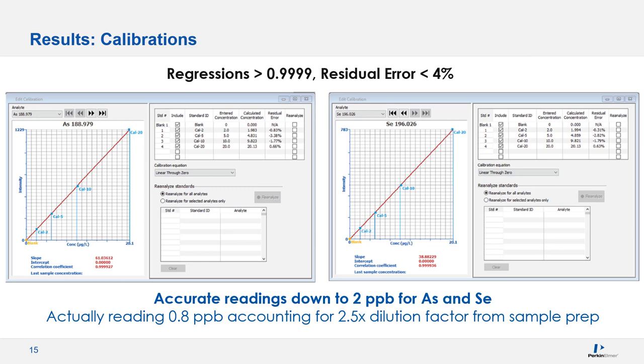Looking at calibration curve results: standards were made at 2, 5, 10, and 20 ppb in 1% nitric before reduction, then diluted 2.5x, so the actual concentrations entering the plasma were lower — the 2 ppb standard becomes 0.8 ppb. Regression values were all 0.999 for both arsenic and selenium, and residual errors were all less than 4%. These curves were reproducibly obtained, confirming we could consistently see low levels.